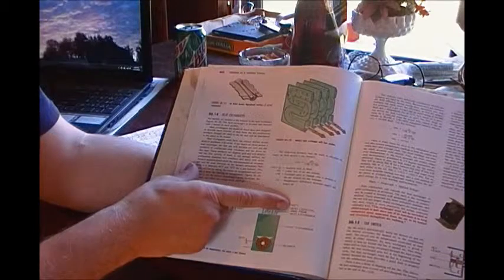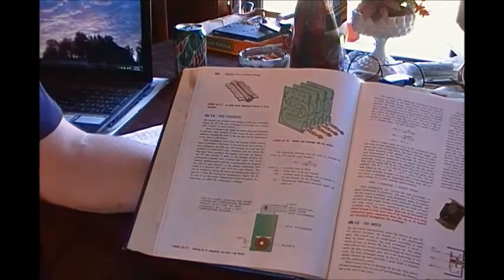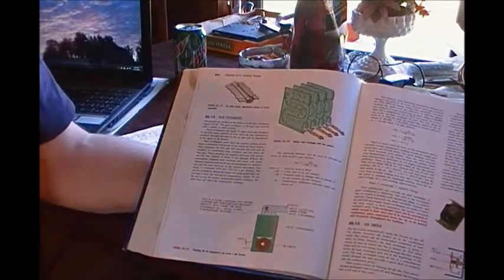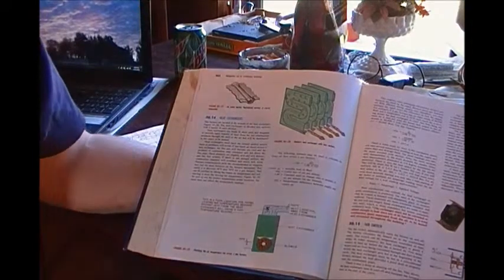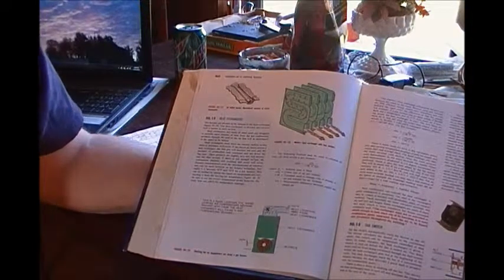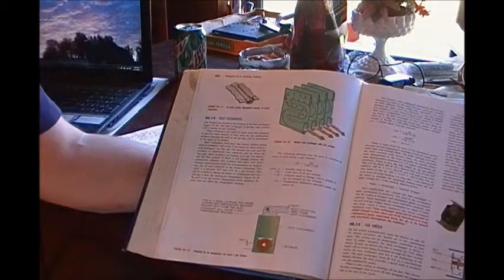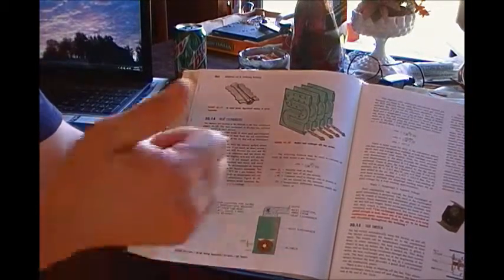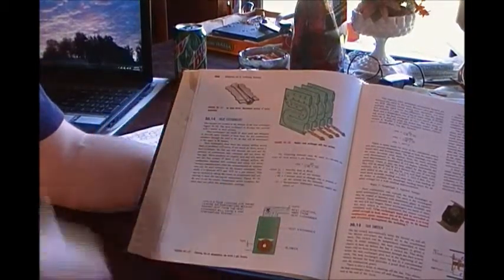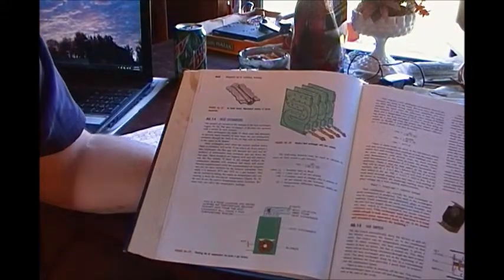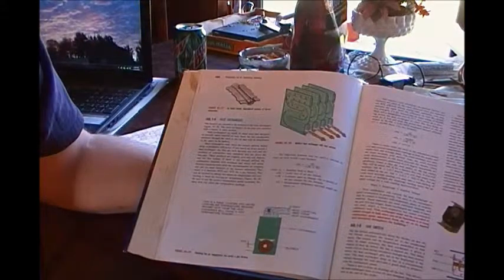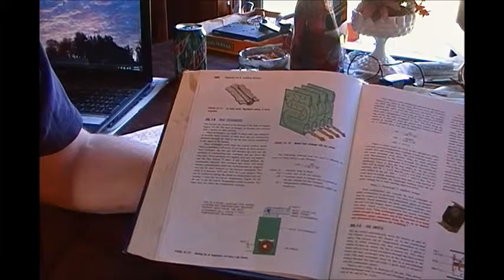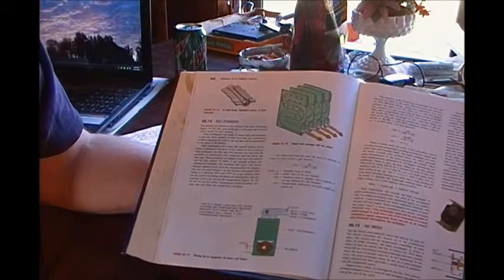Well, now we got to look at the speed of the fan. You may have medium, low, high, low. You might have several different settings. So what you need to do is look at what setting it's on, and of course, if it's reading at 170, then we want to what? Up. We want to go up in speed. We want to push more CFM across that thing. We want to push more RPMs across it. We want to get more air across that coil, and that's going to bring the temperature down.